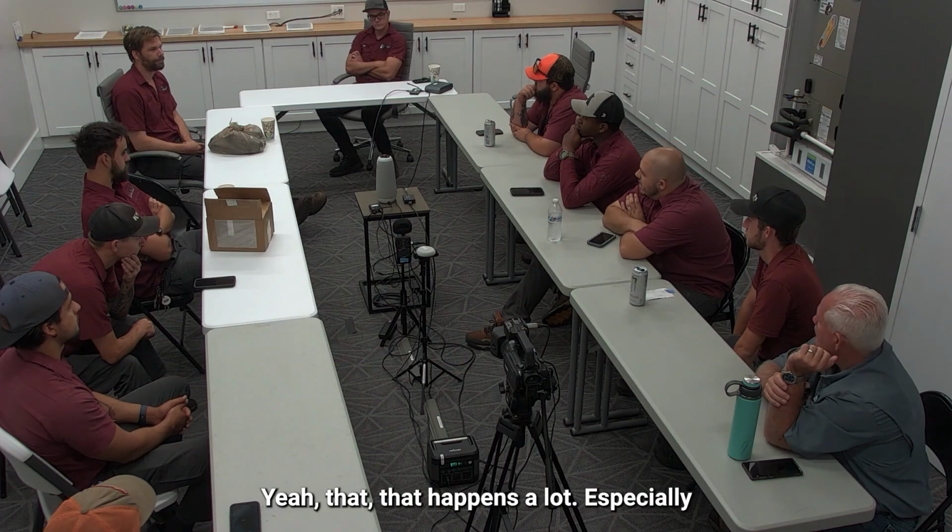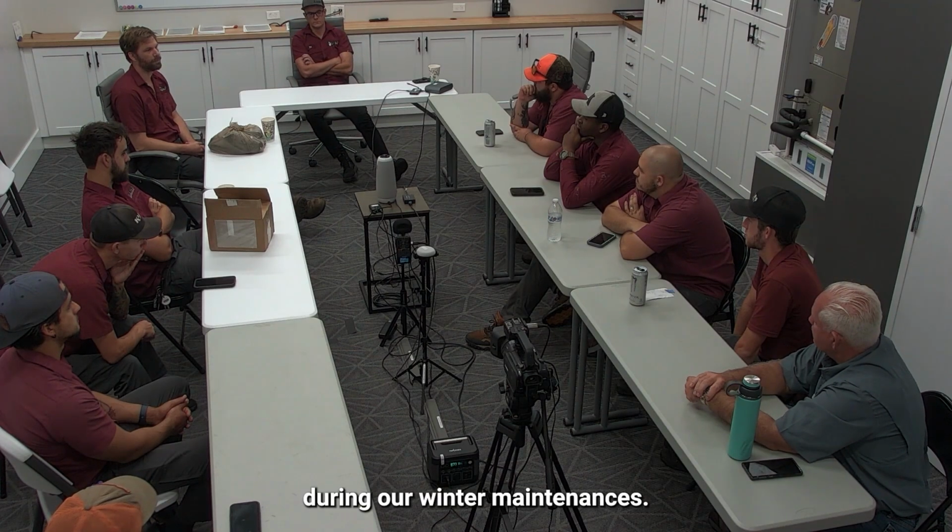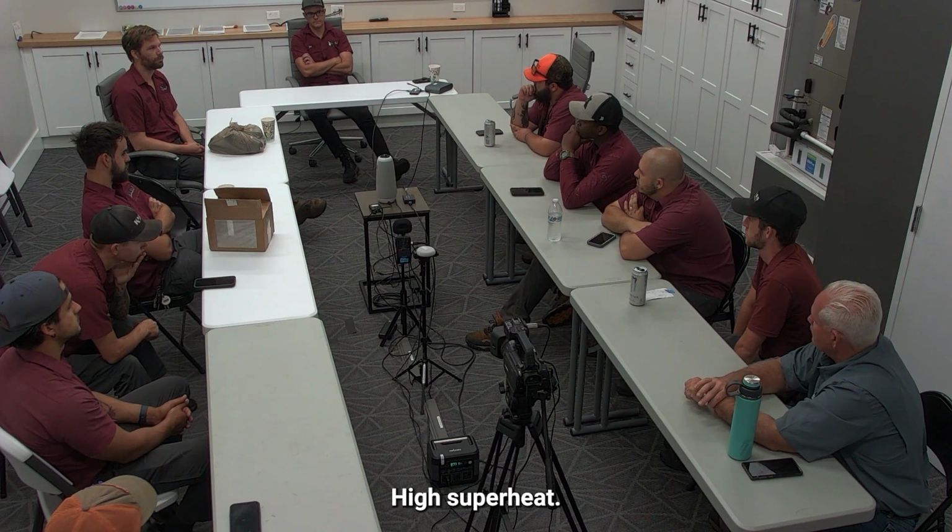Yeah, that happens a lot, especially during our winter maintenances. That's true. High superheat, low subcool. Yeah, that's a huge one for that. You still sometimes have a heat load inside, but outside where the condenser is, it's pretty cold. And that can happen in the rain as well, where your pressures get thrown off.